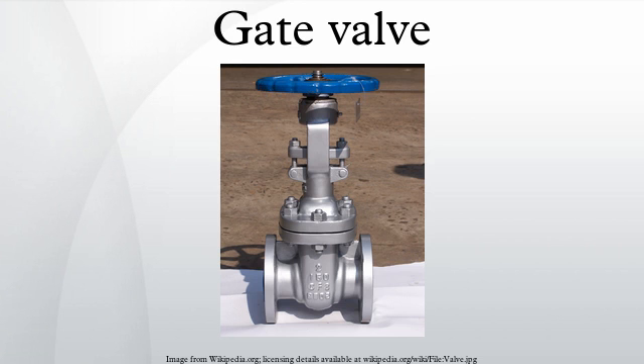Another type of bonnet construction in a gate valve is the pressure seal bonnet. This construction is adopted for valves for high-pressure service, typically in excess of 2250 psi. The unique feature of the pressure seal bonnet is that the body-bonnet joint seal improves as the internal pressure in the valve increases, compared to other constructions where the increase in internal pressure tends to create leaks in the body-bonnet joint.